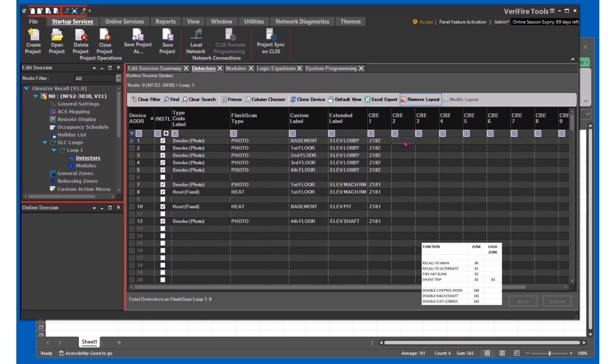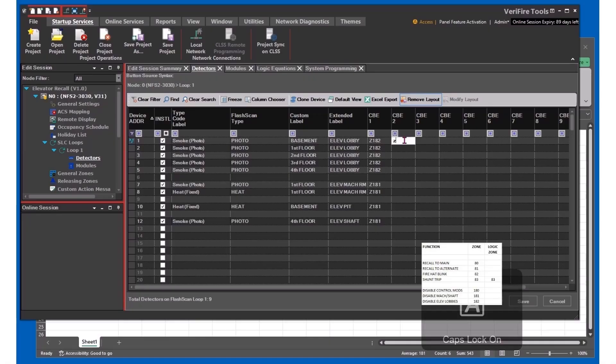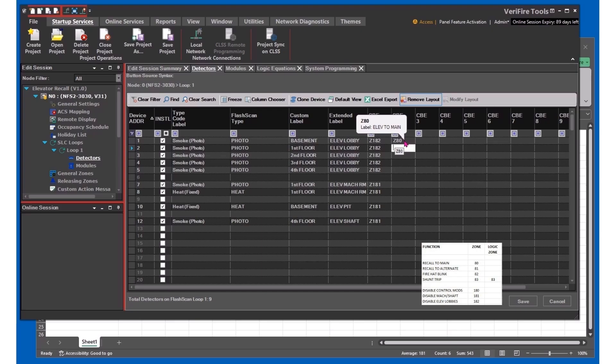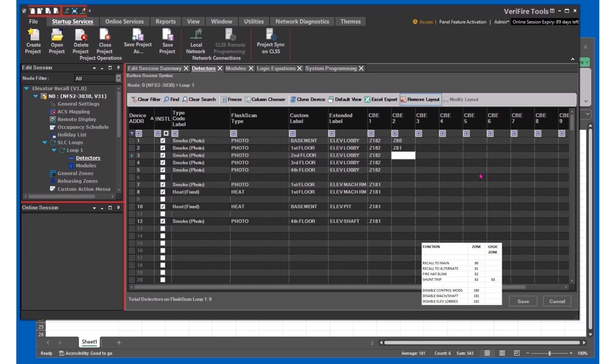For the basement detector, we want to trigger main recall or send the elevator to the main, so we'll put in zone 80. The first floor is going to get zone 81, which will send it up to the alternate landing, and we'll fill in the other floors as you can see.